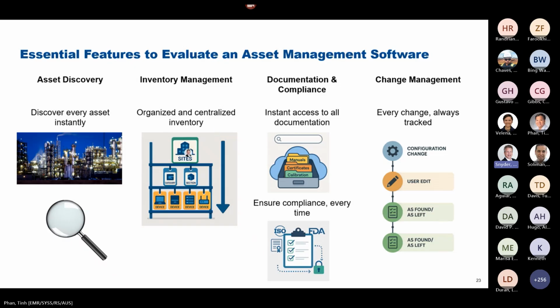But why are you pulling this information in? One reason is documentation and compliance, which goes hand in hand with change management. If we're pulling in all this configuration information, we can see data like what alerts were set or cleared, who logged onto the system, what changes were made, and what the as-found and as-left data were. All of that is accessible through the live device connection, the physical hierarchy, or the logical plant database hierarchy.